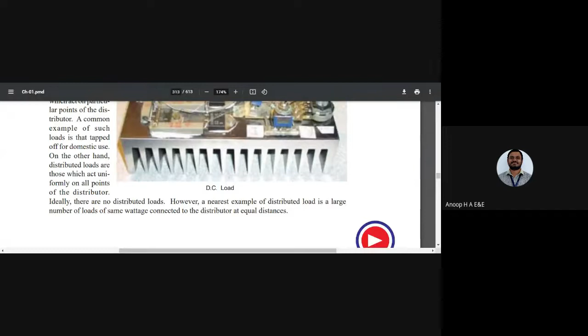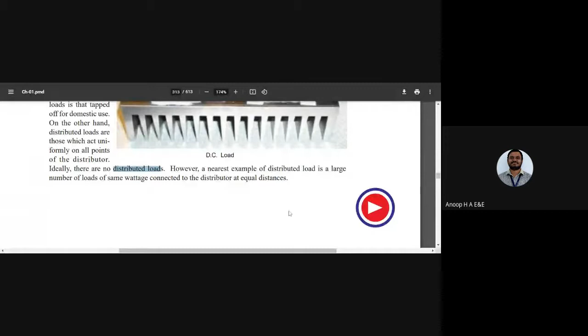Now, distributed loads consist of a large number of loads of the same wattage connected to the distributor at equal intervals. So what are the points you need to keep in mind while working on a DC distribution calculation? How are we going to calculate the power loss, and the voltage? What is the minimum voltage if it is fed at both ends? Depending on the type of loading, we have a derivation to be discussed. The first thing to keep in mind is the determination of the point of minimum potential. So make a note of it.